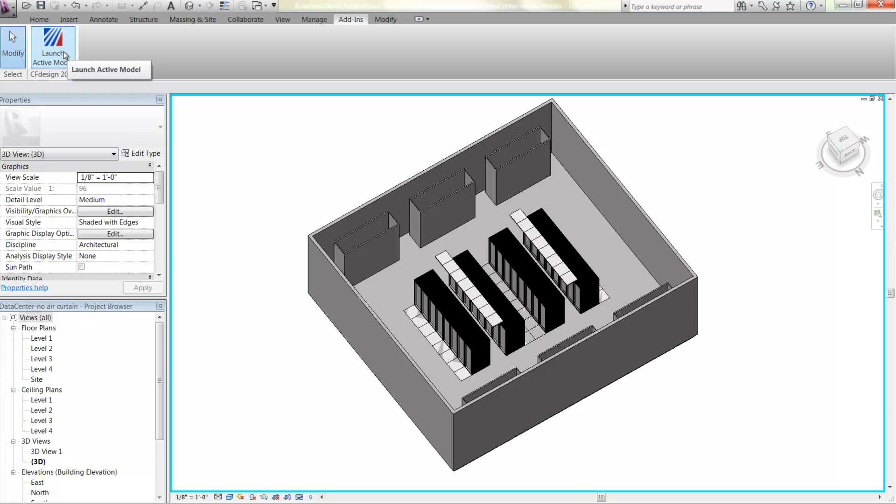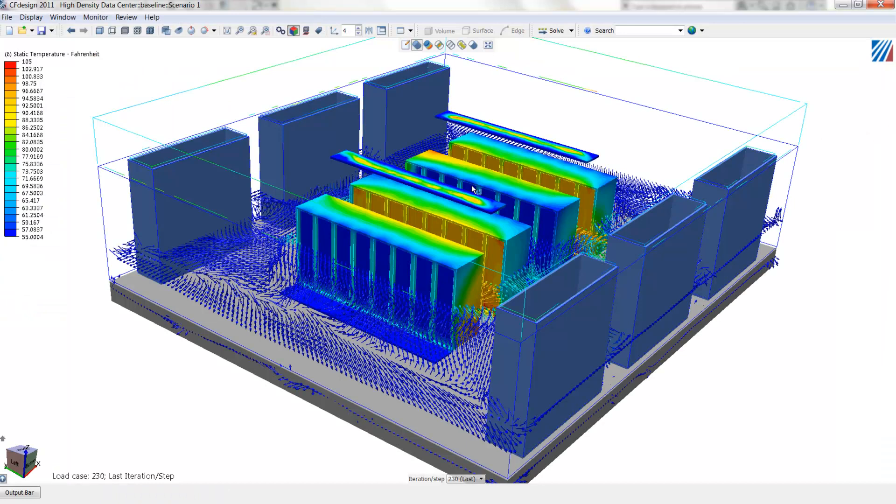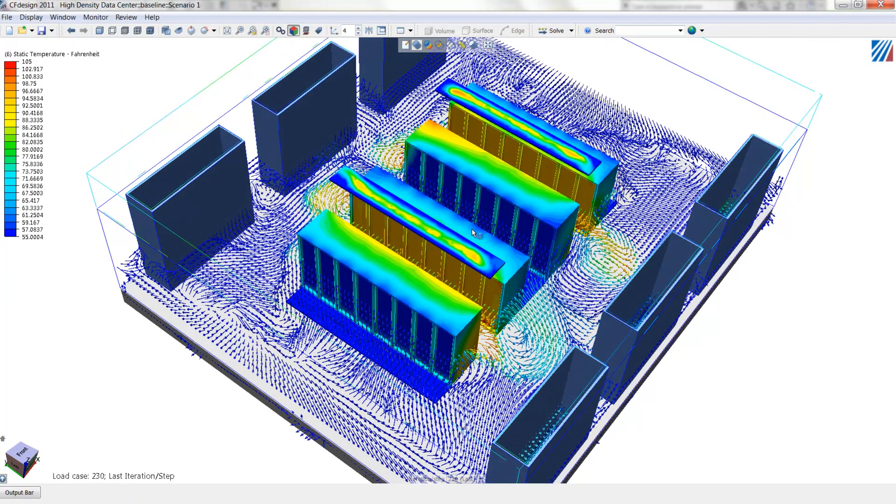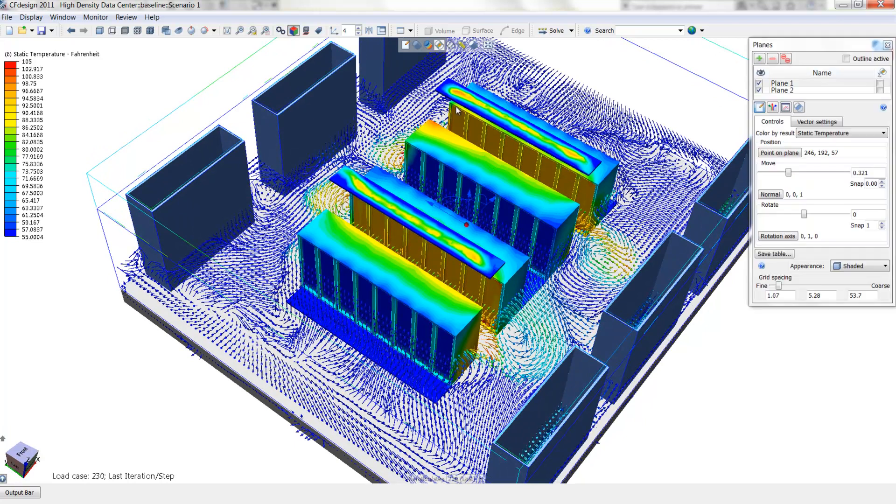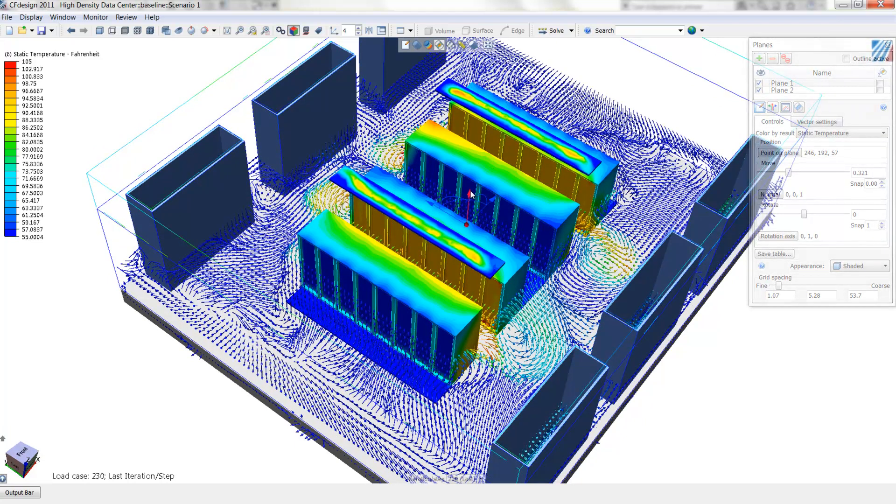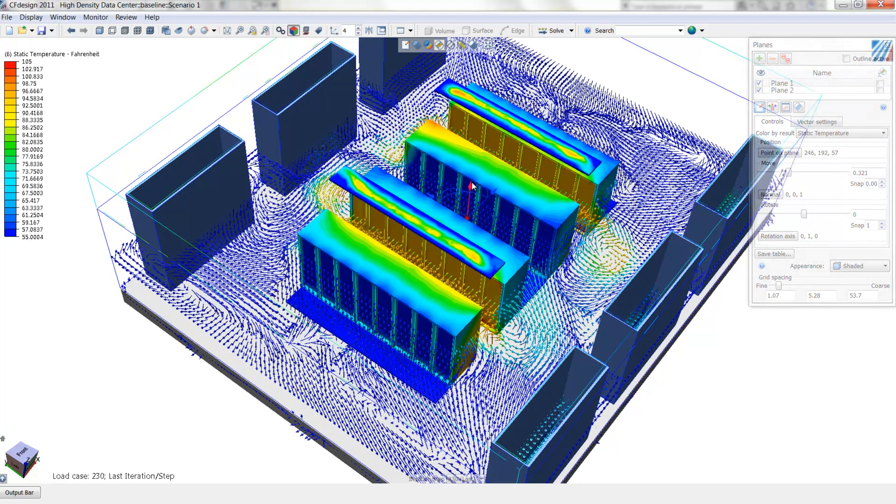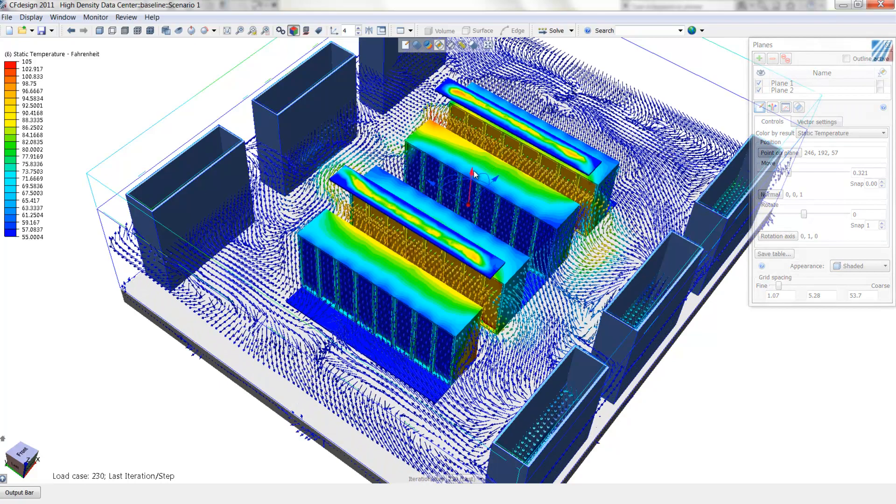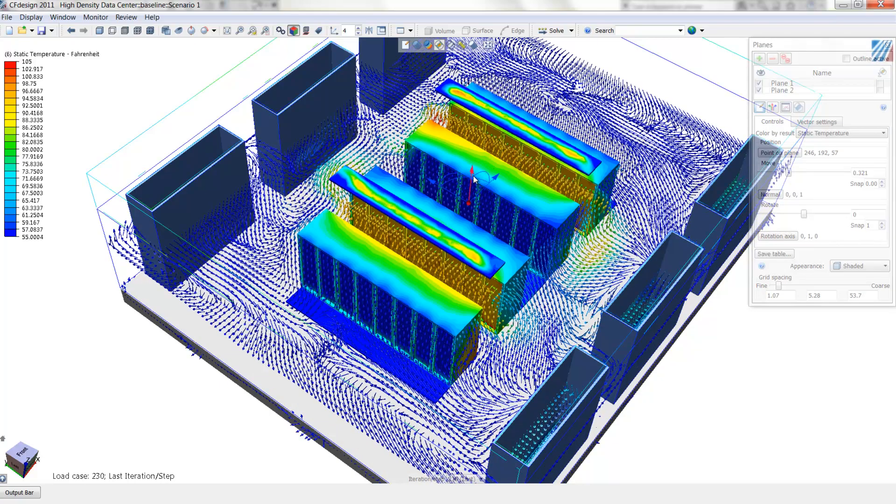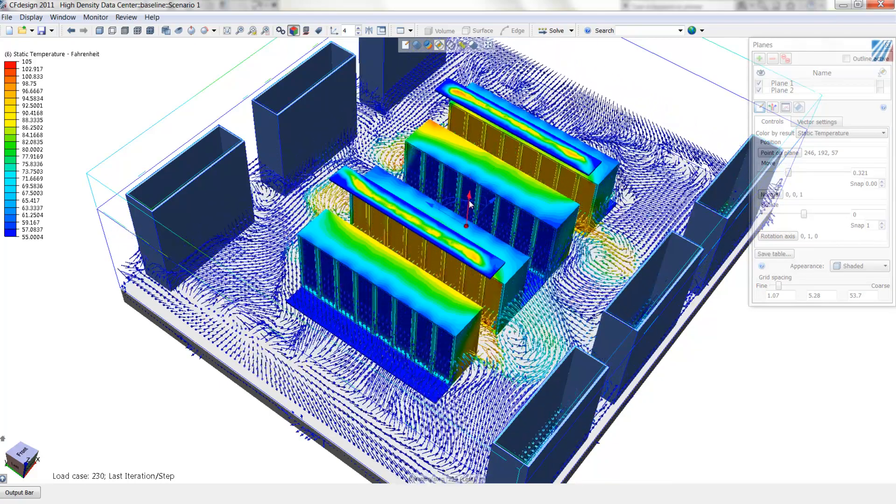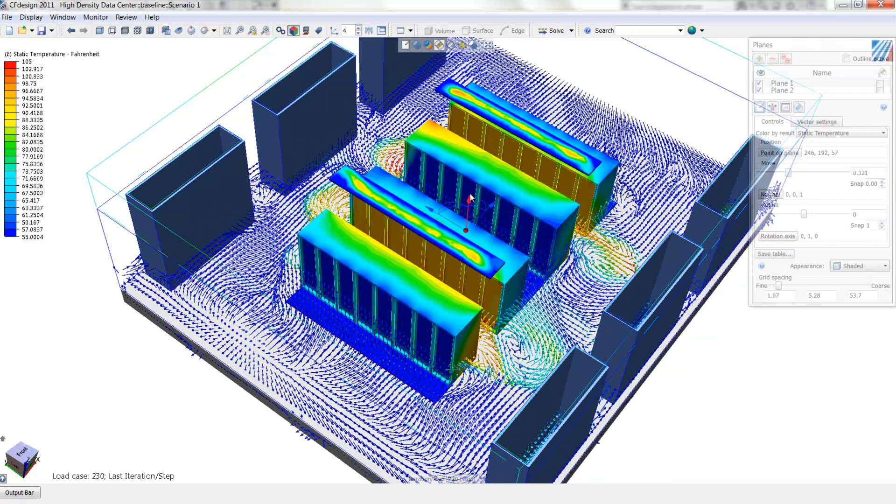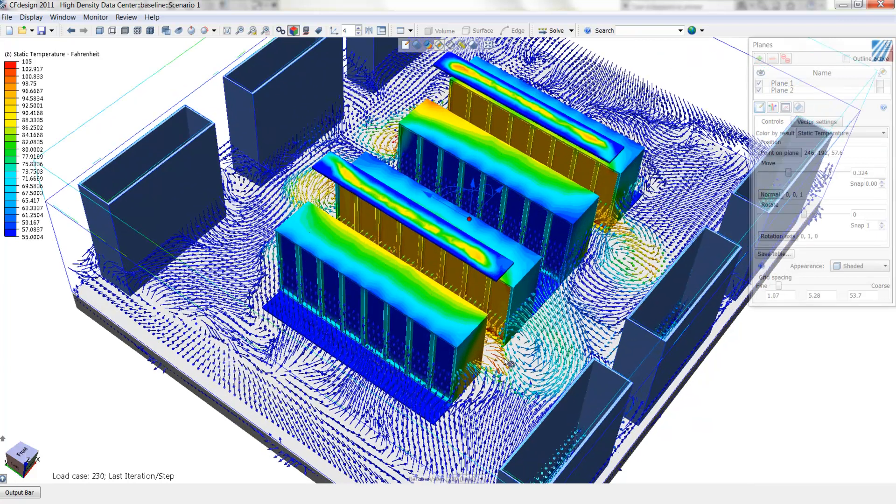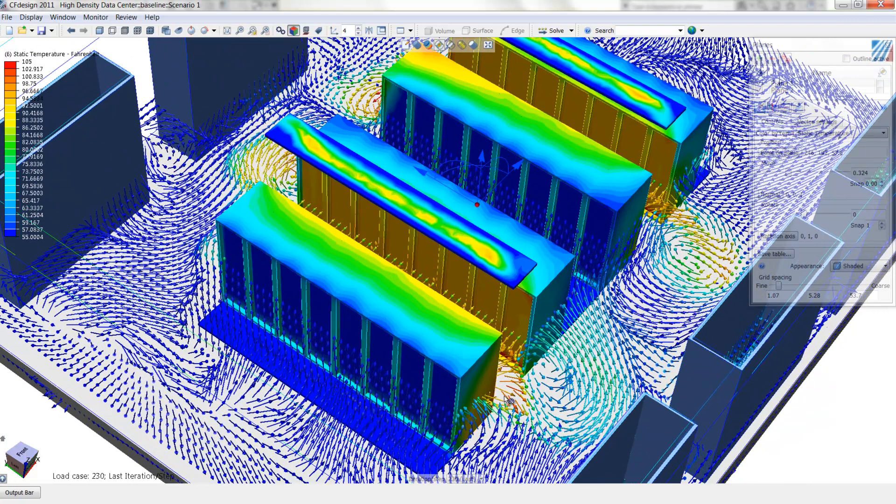Here we see a small server room or data center within Revit brought now into CFDESIGN. We can see within CFDESIGN both temperatures on the actual racks themselves and airflow vectors showing direction and magnitude of the airflow coming out of the server racks. We see on the ends of the aisles, particularly in the middle here, that there is a strong recirculation region, and due to that, we see hot spots within the rack.